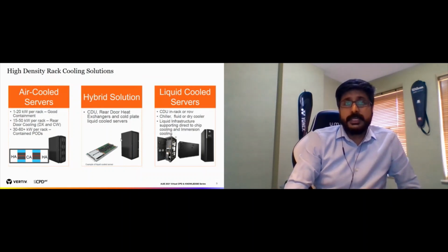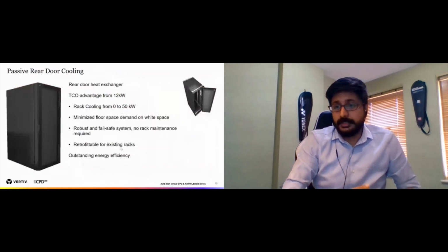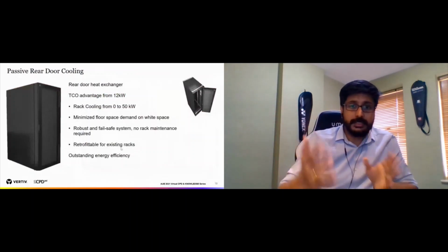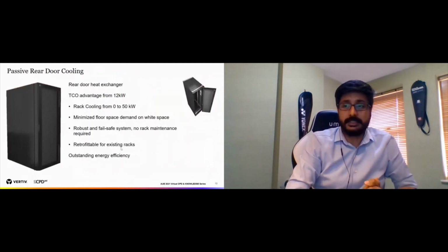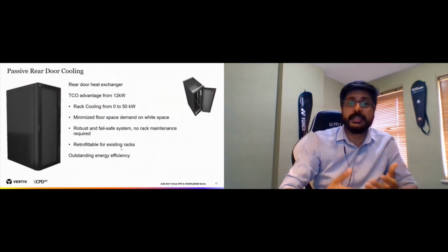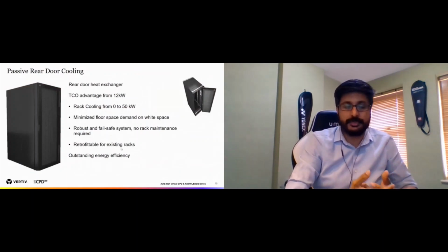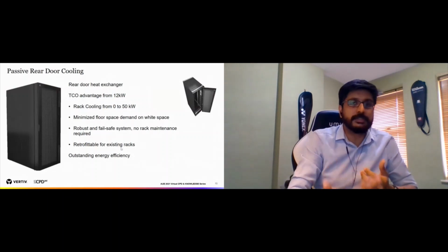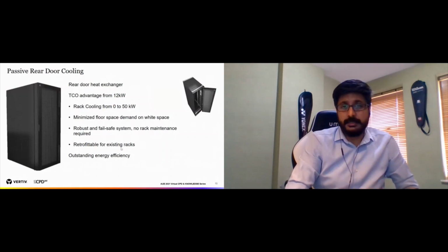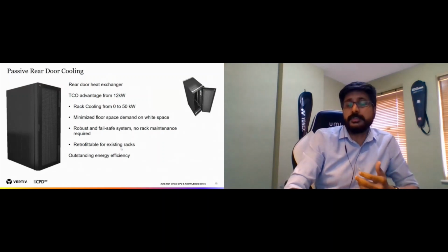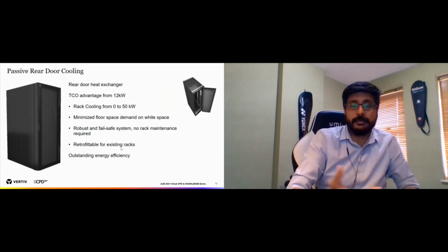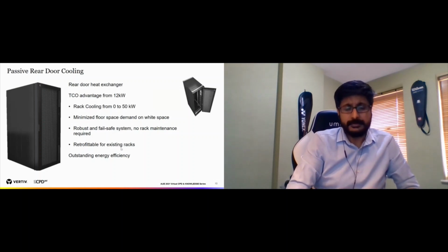Just to give a quick idea on passive rear door cooling, it's basically a chilled water coil sitting right against a rack, and that can give you cooling of up to 35 kilowatt. It utilizes the fan power of the servers themselves, so there are no additional fans or additional input coming into the server rooms. That means the efficiency keeps increasing, or you can keep the same efficiency, and you still get the amount of cooling that is needed.